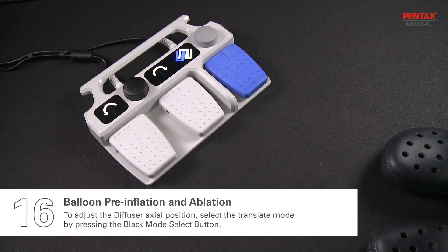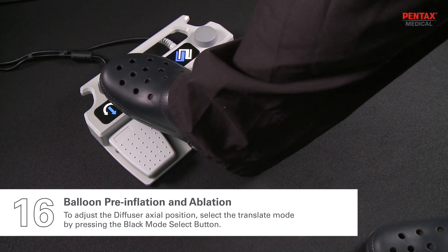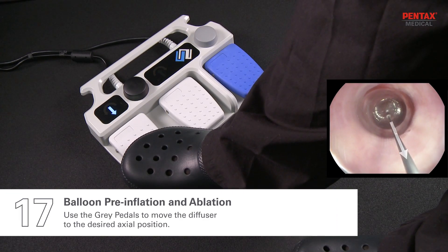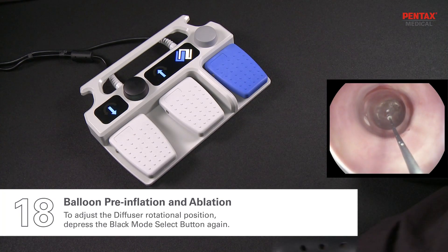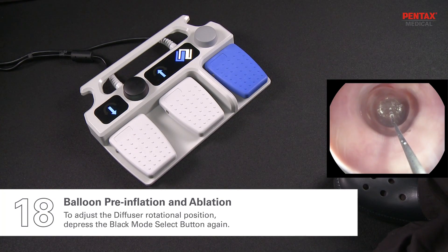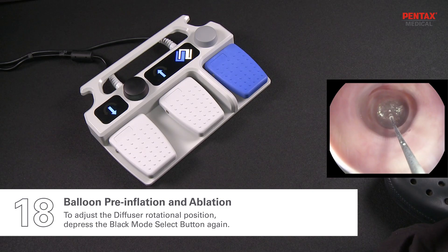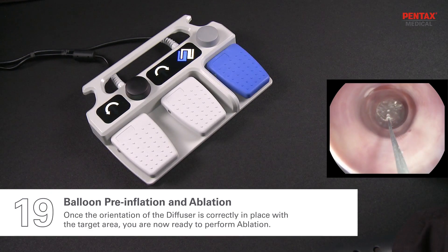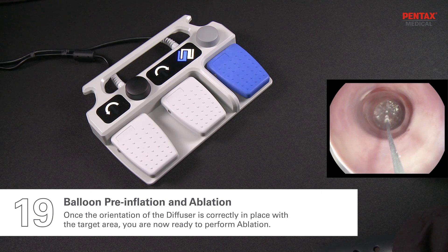To adjust the diffuser axial position, select the translate mode by pressing the black mode select button. The foot pedal will display arrows pointing up and down. Use the gray pedals to move the diffuser to the desired axial position. To adjust the diffuser rotational position, depress the black mode select button again. Rotational arrows indicating clockwise and counterclockwise direction will be illuminated. Once the orientation of the diffuser is correctly in place with the target area, you are now ready to perform ablation.